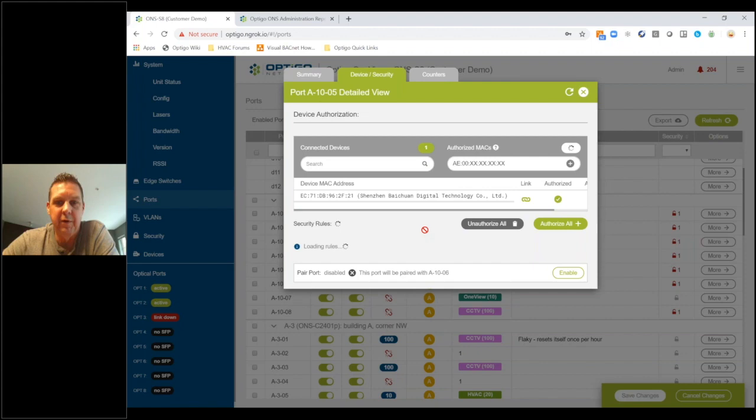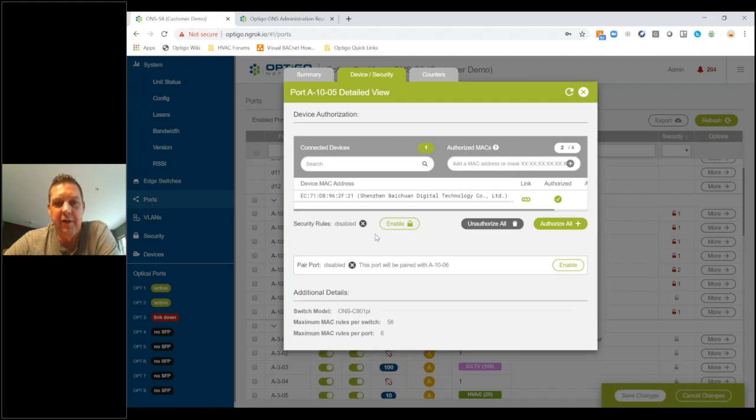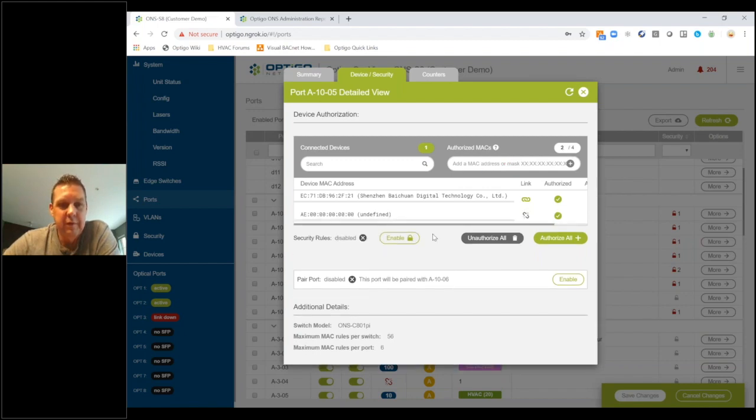So anything specified with an AE, I'm not sure whose MAC address out in the world that is, but anything in there, I can apply the security rule to it. And what that means is any device that doesn't have this AE will automatically not be able to get to the system. So you could take whoever has reserved MAC addresses out in the field, like Distech, Delta, JCI, Honeywell, they all do the same thing. Then you could reserve the system just to put that in here.